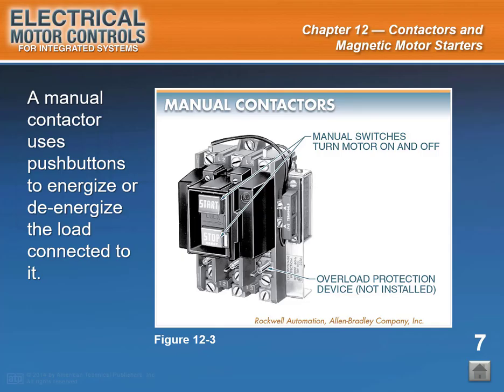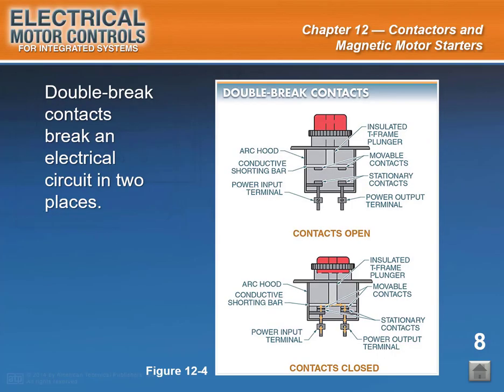Start of Slide 7. A manual contactor uses push buttons to energize or de-energize the load connected to it. See Figure 12-3. A manual contactor manually opens and closes contacts in an electrical circuit. Manual contactors cannot be used to start and stop motors because they are missing overload protection that should be built into them for starting motors. Manual contactors are normally used with lighting circuits and resistive loads such as heaters or large lamp loads. A fuse or circuit breaker is normally included in the same enclosure with a manual contactor. End of Slide 7.